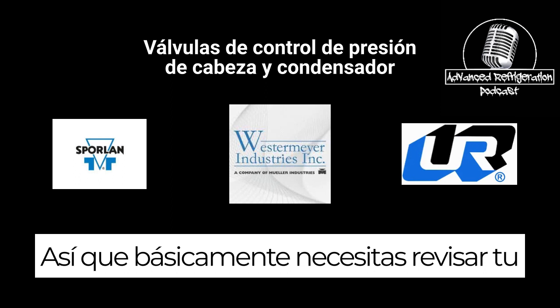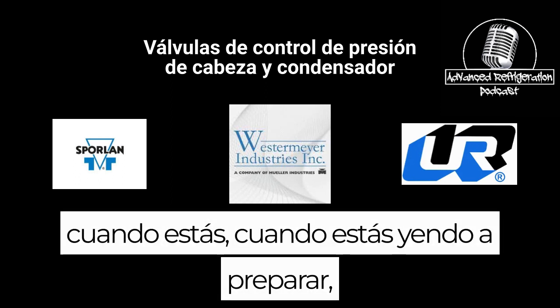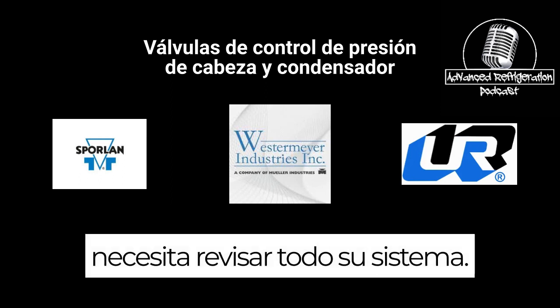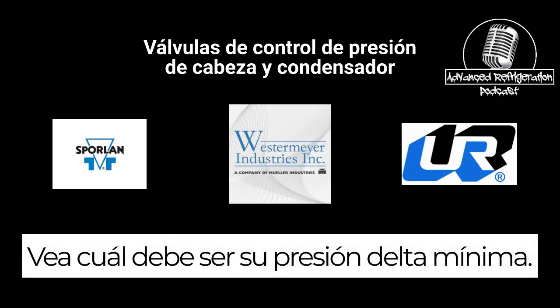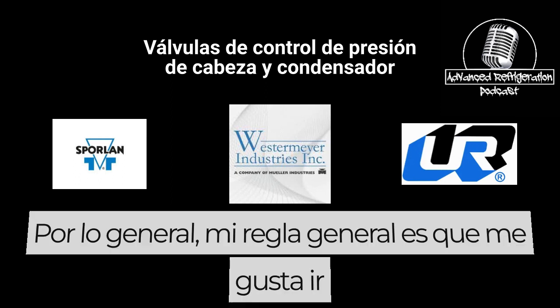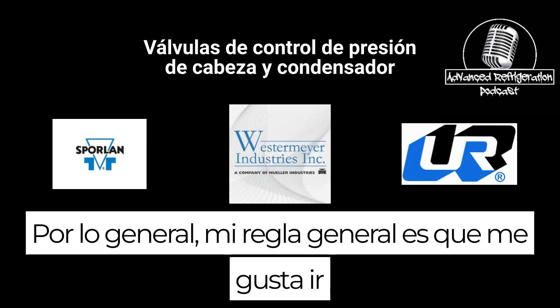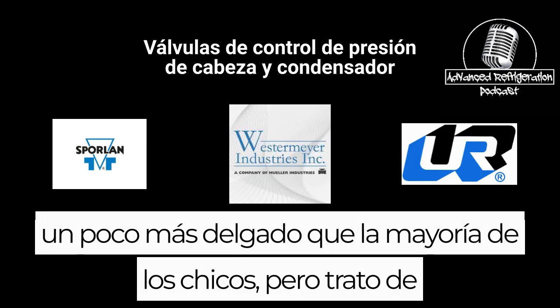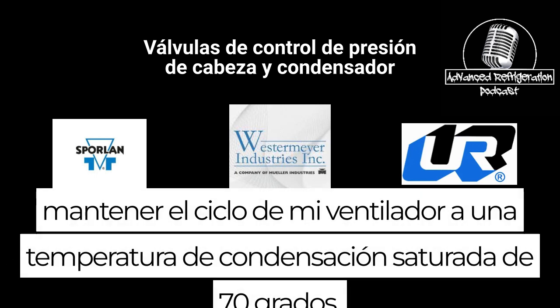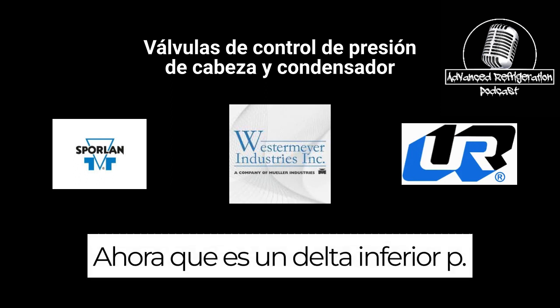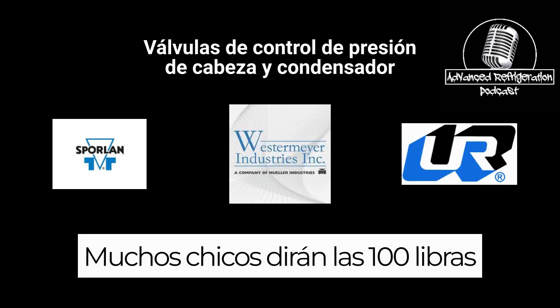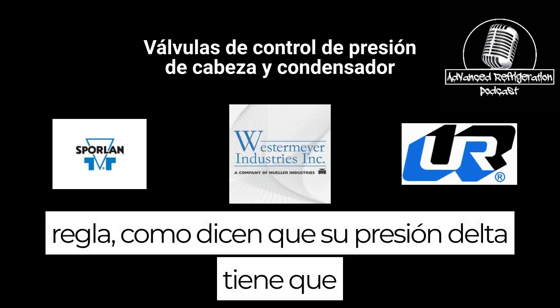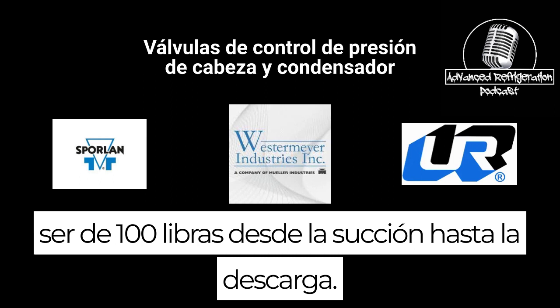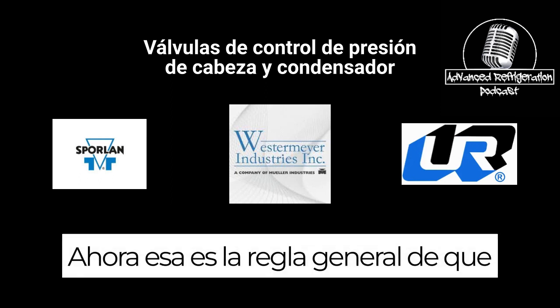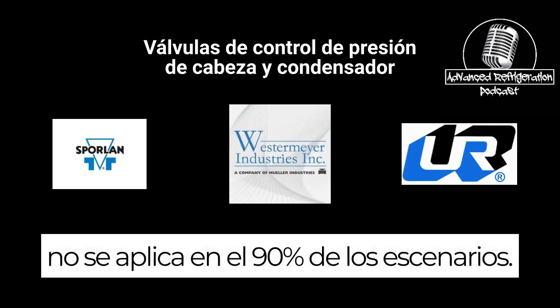Yeah. So basically when you're going over setting up fan cycling, you need to look over your entire system, see what your minimum delta pressure needs to be. So generally, my rule of thumb is I like to go a little more lean than most guys, but I try to maintain my fan cycling at a 70 degree saturated condensing temperature. Now, that is a lower delta P. A lot of guys will say the 100-pound rule. Like they say your delta pressure has to be 100 pounds from suction to discharge. Now, that is rule of thumb. That doesn't apply in 90% of scenarios.